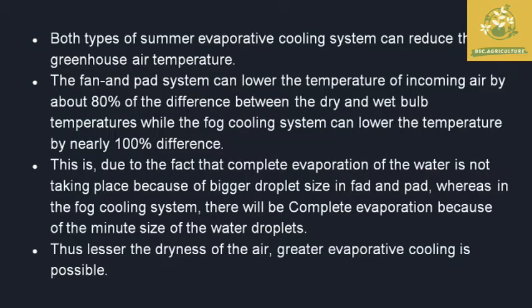If you use the fog cooling system in the greenhouse, you can reduce air temperature. The fan-and-pad system can achieve up to 80% of the theoretical cooling effect, while the fog cooling system can maintain up to 100% of the temperature reduction potential.